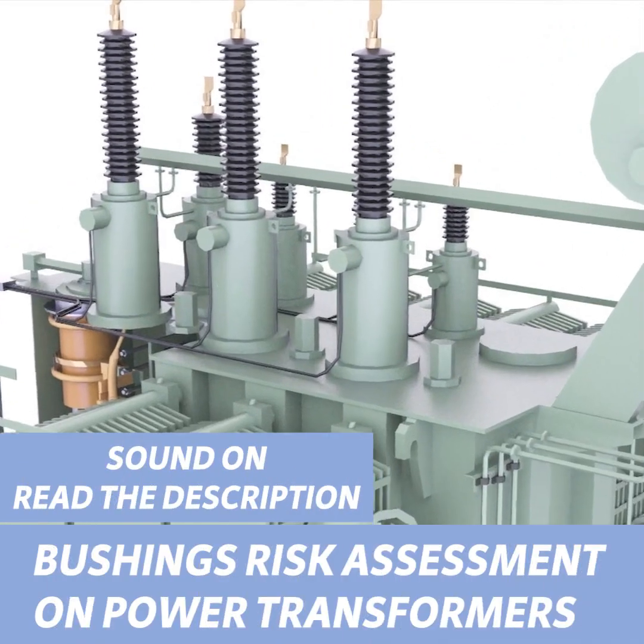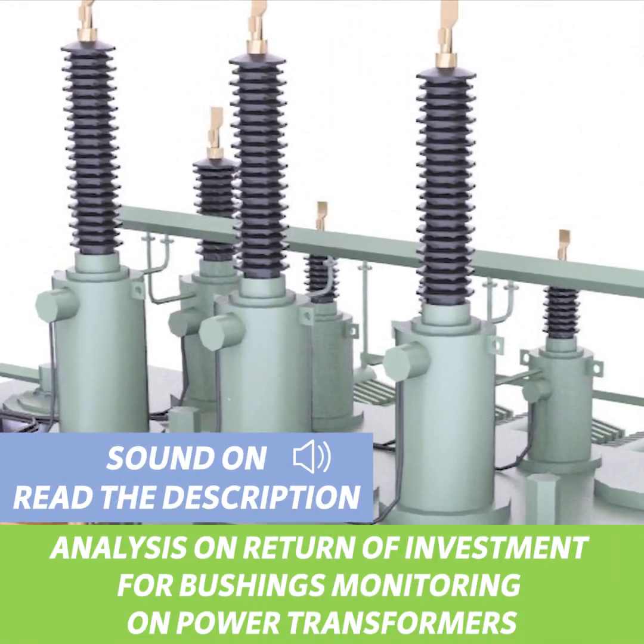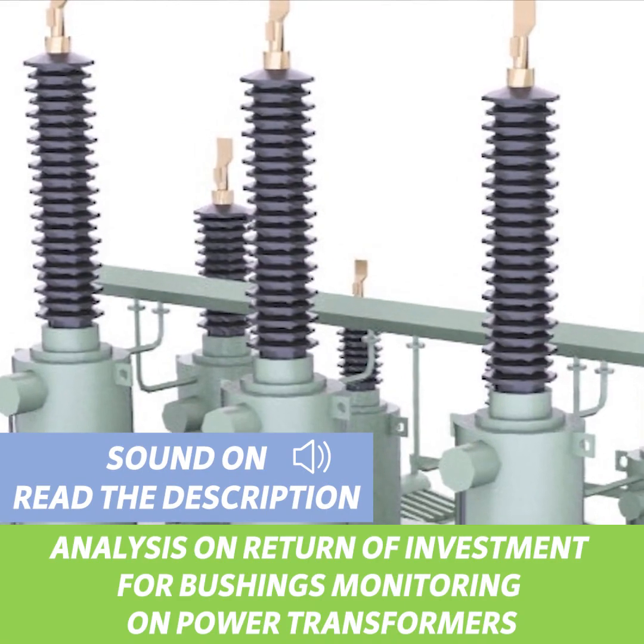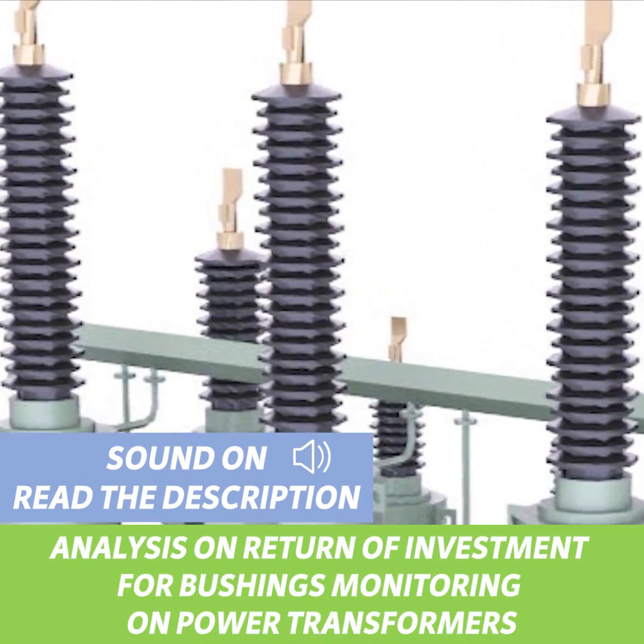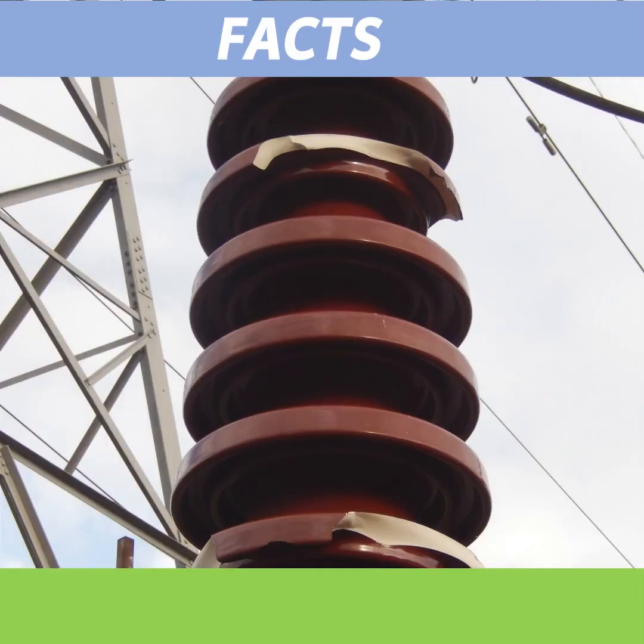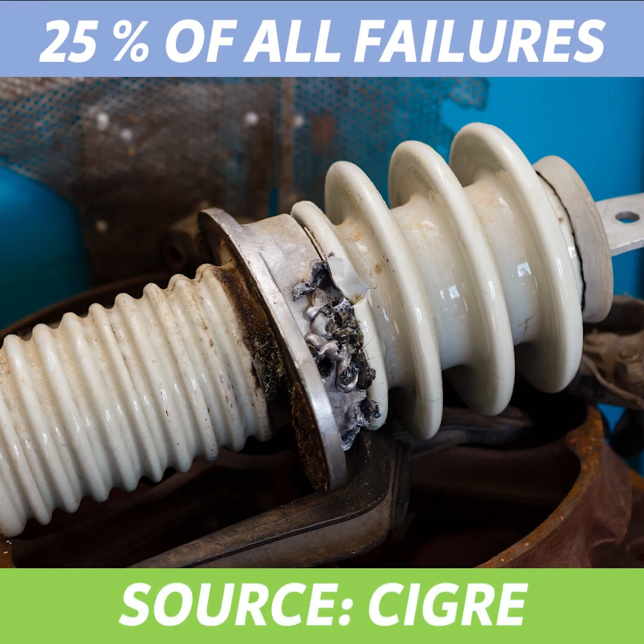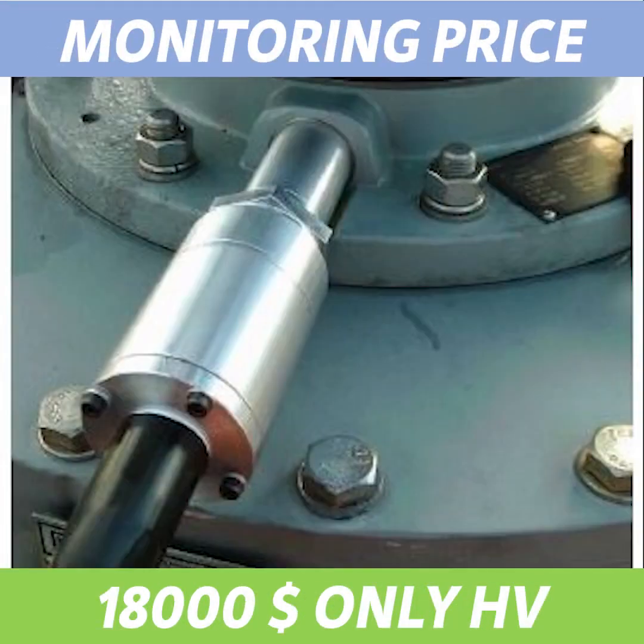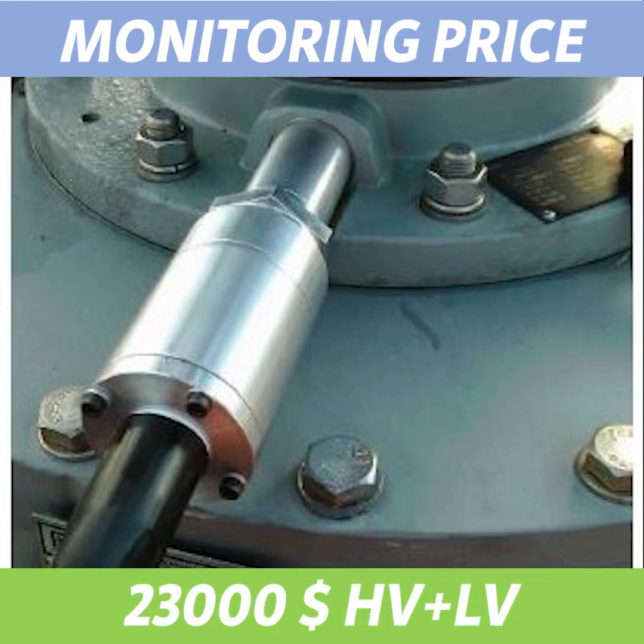Bushings risk assessment on power transformers and analysis on return of investment for bushings monitoring on power transformers. Facts. Bushing failure is among the most frequent causes of transformer failure, greater than 25%, source CIGRE. Bushings monitoring price: $18,000 US, just HV side; $23,000 US, HV and LV side.